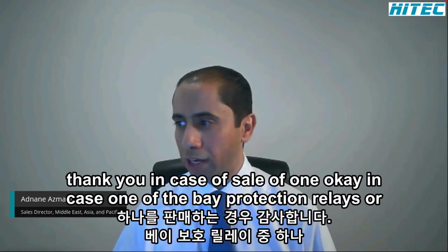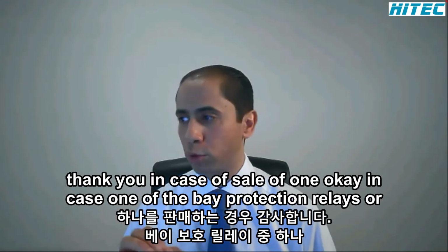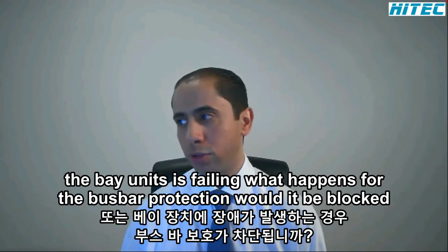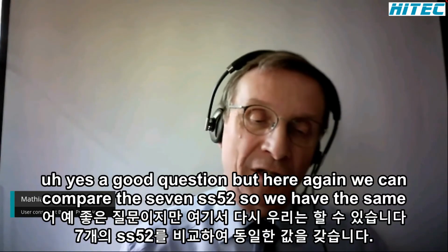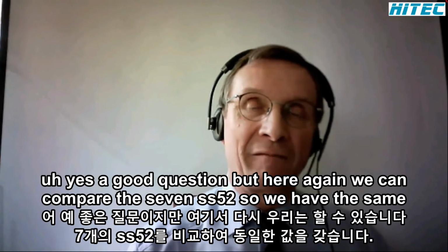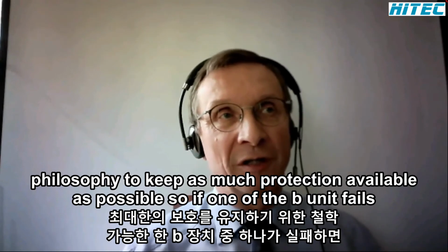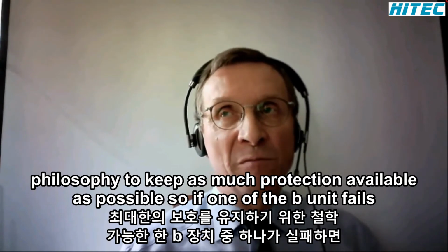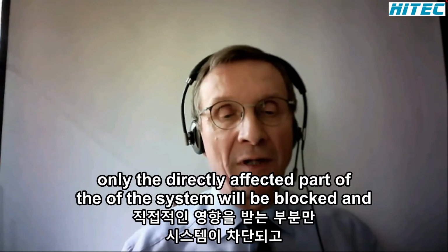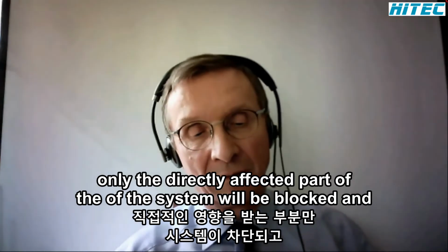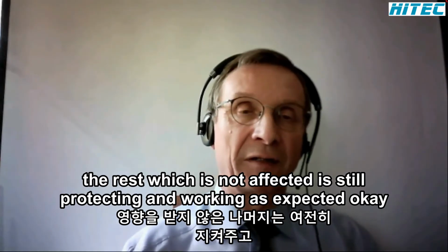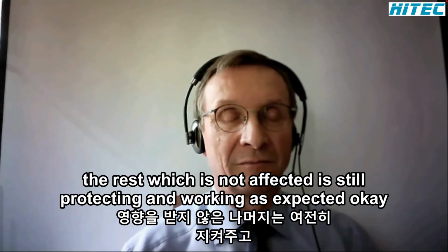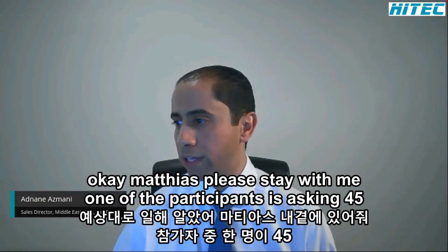Matthias, back to you. In case one of the bay protection relays or bay units fails, what happens to the busbar protection? Would it be blocked? Yes, good question. Here again, we can compare with the 7SS52. We have the same philosophy to keep as much protection available as possible. So if one of the bay units fails, only the directly affected part of the system will be blocked, and the rest, which is not affected, is still protecting and working as expected. Okay, perfect.